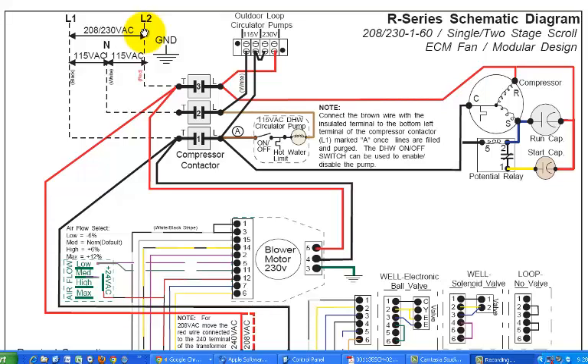Not to scare you away, but it's not something to jump into unless you have that understanding of the safe use of the voltmeter, etc., or it could be a trouble light as well, although certainly from a technical perspective, the voltmeter is probably more widely used. But do be safe. Across the L1 and L2 then, if we were to measure that with our voltmeter, we're going to have that 230 or so volts.